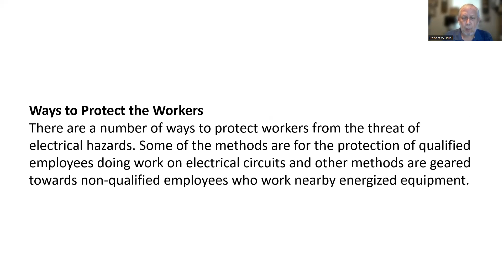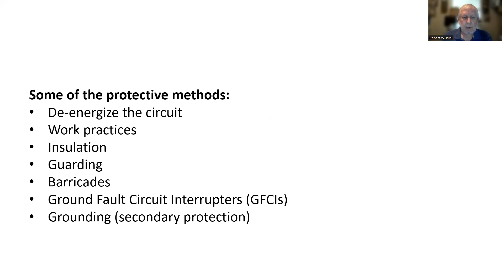Now, ways to protect the worker. There are a number of ways to protect workers from the threat of electrical hazards. Some of the methods are for the protection of qualified employees doing work on electrical circuits, and other methods are geared towards non-qualified employees who work near energized equipment. Some of the protective measures: de-energize the circuit. That's the main thing you want to do, de-energize the circuit. Work practices, insulation, guarding could come into play, barricades, ground fault circuit interrupters, GFCIs, or grounding, which would be a secondary protection.